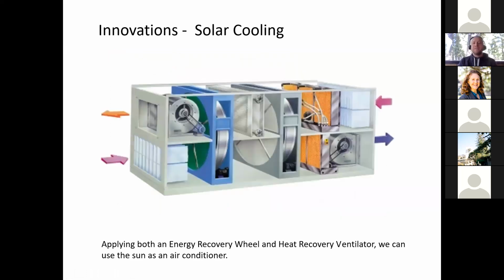So here's what that system looks like in an actual box that you can buy and stick on your building. But all of those pieces go in together. Again, no compressor, so very low energy. Really, there's only 3 or 4 things that are using energy. There's 2 fans, which your building has anyway. There's 2 little motors that turn the heat wheel and the desiccant wheel. And then there's a little pump that drives water into the evaporative cooling sections. So very, very low energy compared to a traditional air conditioner.